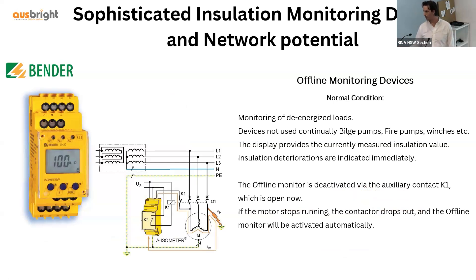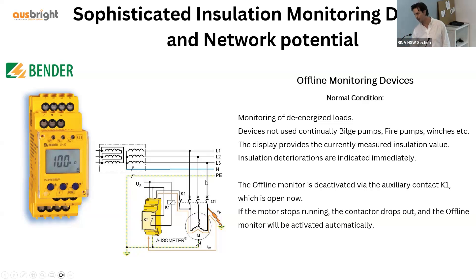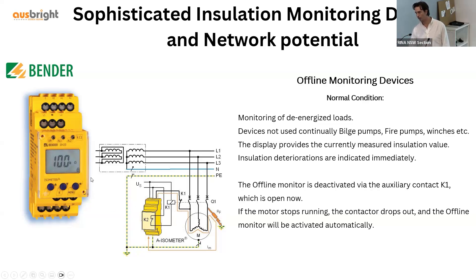This is another type of insulation monitoring device. Devices are only as good as if they are connected to a piece of equipment. If you have a motor that isn't running continuously — like a winch, fire pump, or bilge pump — it could be sitting unused for months with an air gap at the starter. Earth monitoring systems can't see through an air gap; if there's no continuity, you can't measure anything. This offline monitoring device sits after the starter and continually monitors the motor for insulation breakdown, making it suitable for majority-offline equipment.